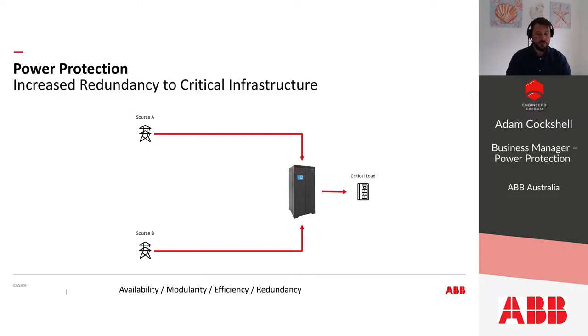In this illustration here, you can see a source A and a source B being directly fed from the grid. In this instance here, we're adding an AVC to source A, so to provide some form of power conditioning. Supplementing the AVC in this instance for a UPS on source A, more commonly used with a UPS on source A and source B. It's illustrating the different applications that an STS can be used in.